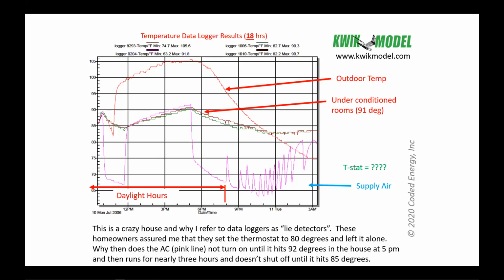Mm-hmm. Yeah, there's other things that come into play too. Your ducts get colder. A lot of these ducts are running through, you know, between floors and in the walls and stuff like that. And those walls start getting colder. And so your supply temperature continues to drop and drop and drop. But if you were to also monitor the SEER rating of an air conditioner over time, the SEER rating gets better the longer it runs, okay? And it takes a while to hit that. You know, if it's rated for 16 SEER, it takes a while to get that 16.